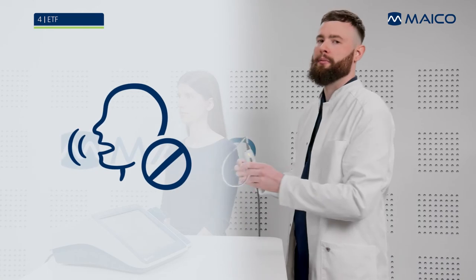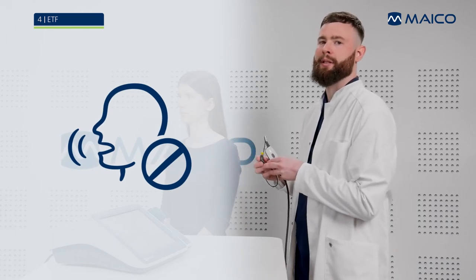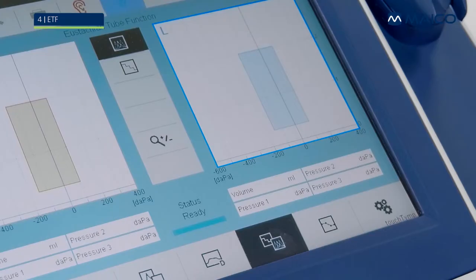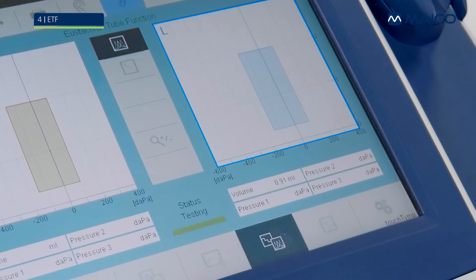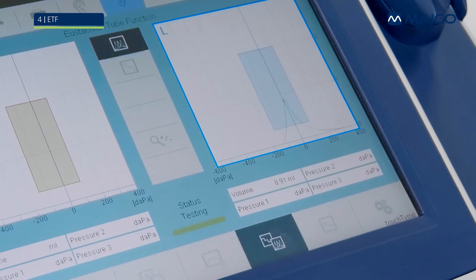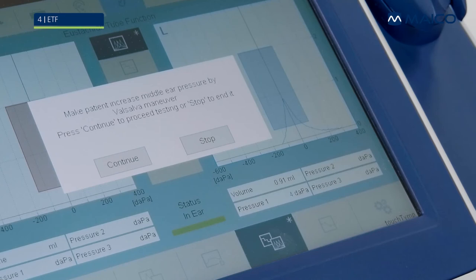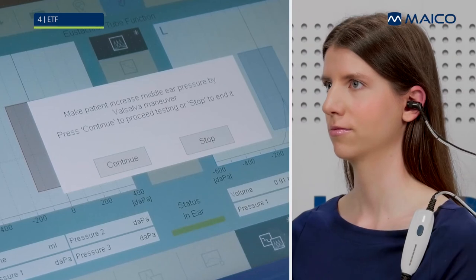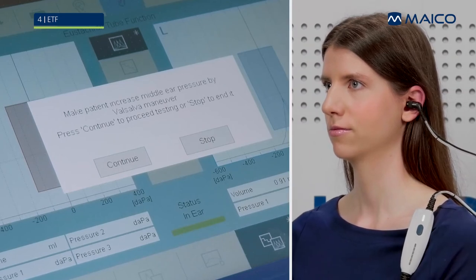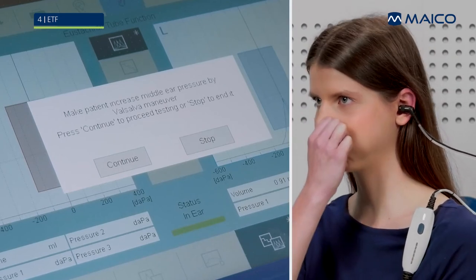Before testing begins, instruct the patient not to move or talk until the measurement is completed. Any sound or movement may give unreliable results. As the test is progressing, the numerical information below the graph is displayed. Once the first tympanogram is complete, the pressure at the maximum compliance appears under pressure 1. The first message is displayed instructing the patient to perform a swallow or Valsalva maneuver.